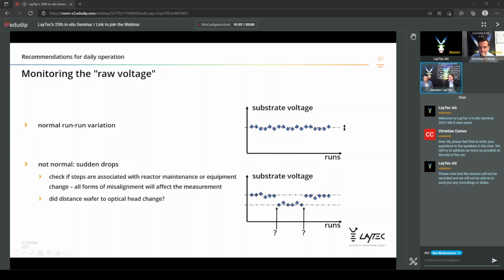If this is returning, or you need, first of all, we need to check the distance to the optical head, the position. And what Heiko explained as well is probably the fiber cable has been broken, the glass fiber. So that might change suddenly, or it will change suddenly, but at least by opening and closing the reactor already, the fiber is moving a little bit.